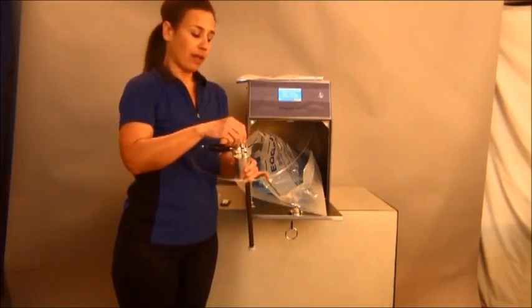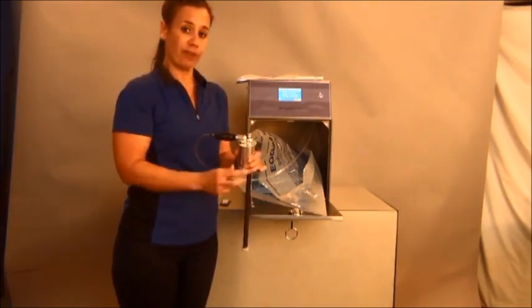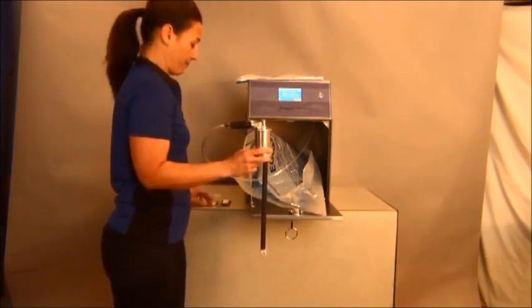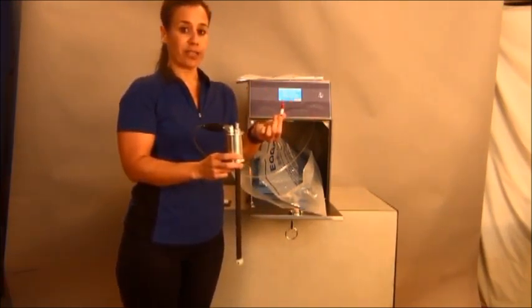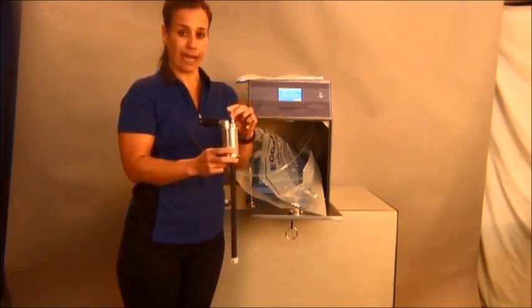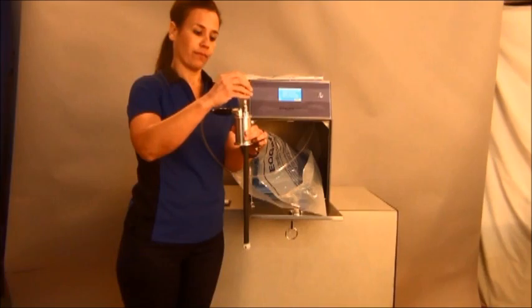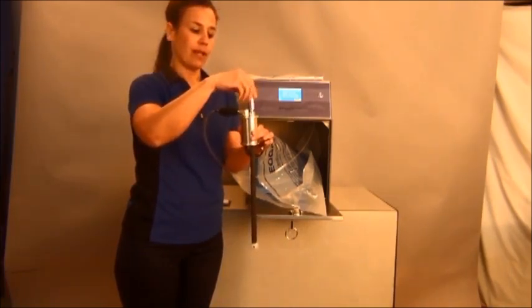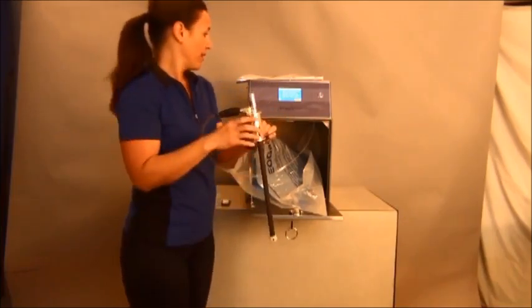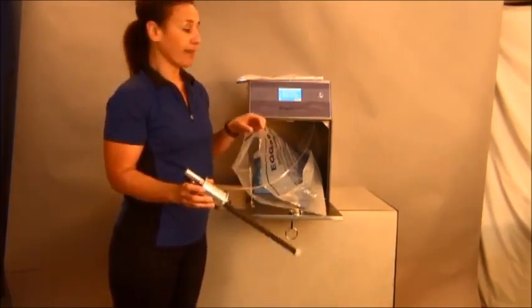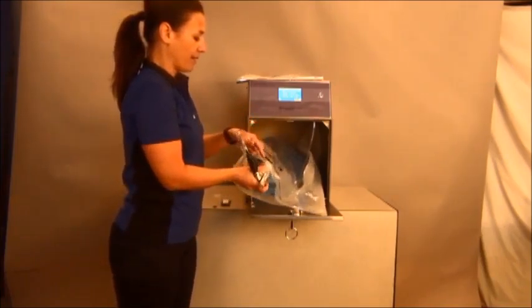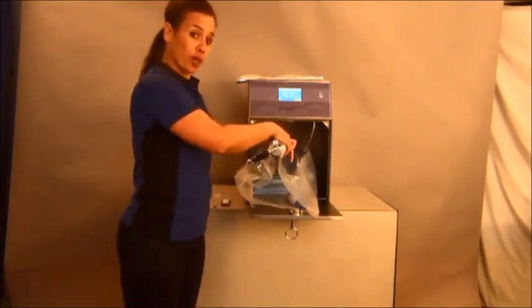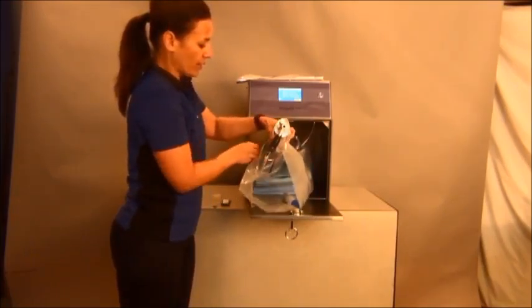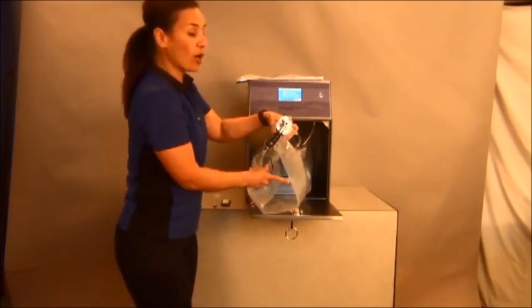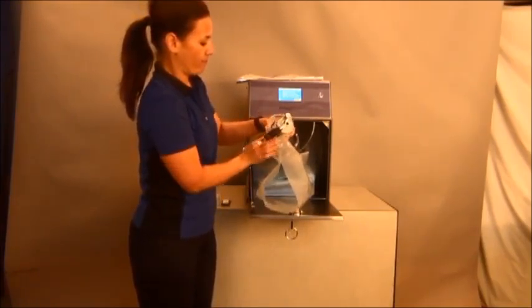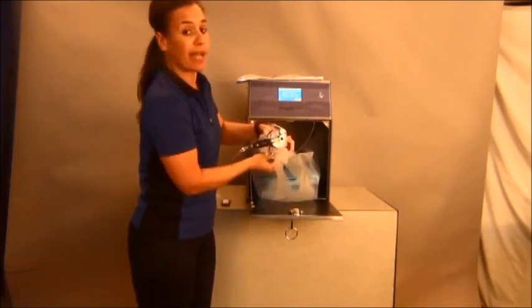At this point in time, I'm going to open my process challenge device to add my biological indicator. Your biological indicator has the red top, which goes in the downward position. And you simply screw the top back on. The final step is to close the bag over the purge probe. Again, going about 4 inches down the liner bag, you want to cinch your liner bag around the silver bobbin, making sure that you don't have any gaps.